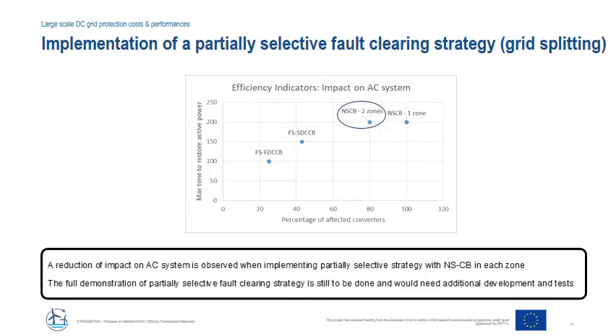The potential reduction of the impact on the AC system which is obtained by implementing a partially selective strategy is illustrated here by the displacement of this protection strategy towards the lower potential impact area, lower left side, in the assessment reference frame proposed here. This example illustrates the potential interest of implementing a partially selective fault clearing strategy for large-scale DC grid protection. However, the full demonstration of such partially selective strategies is still to be carried out and will need additional development and tests.